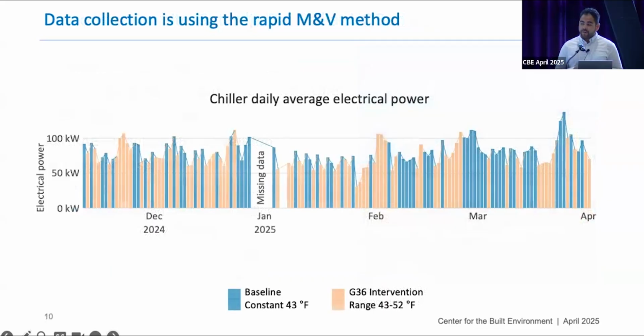So we started data collection in November, and we are still currently collecting some more. We are using the rapid M&V process data collection method that we presented in previous CBE meetings. With this method, we are randomly switching between the baseline control and the intervention to reduce the confounding factors such as changes in occupancy, operation, and weather. So in theory, we get at an answer much quicker on what is the savings potential of these control strategies. So this plot gives you an idea of the back and forth between the different control strategies. The baseline control is set to maintain a constant 43 degrees Fahrenheit for the chilled water temperature. And the Guideline 36, like I said, is ranging from 43 all the way up to 52, depending on the demand.